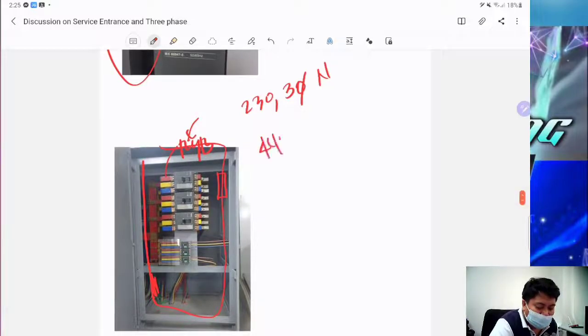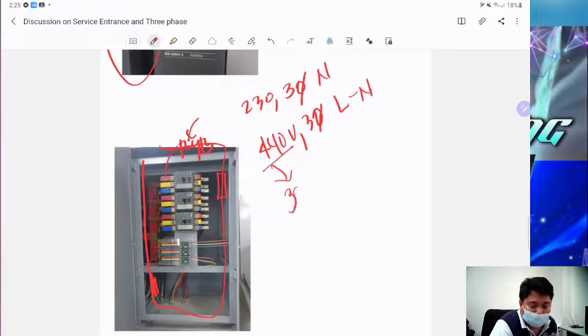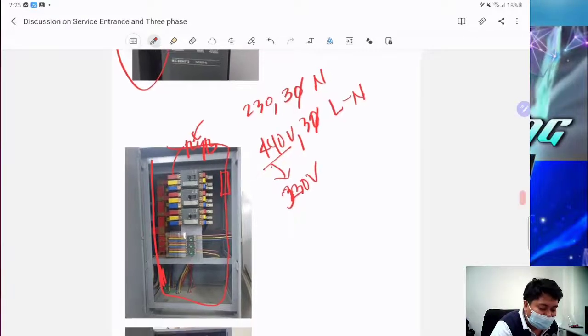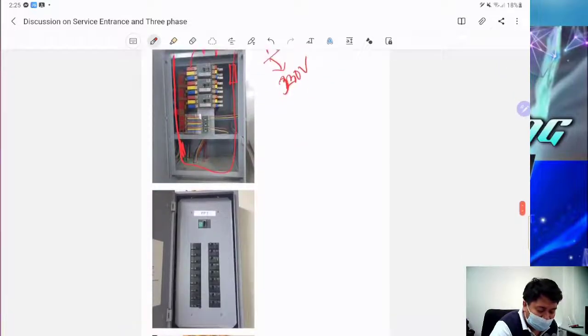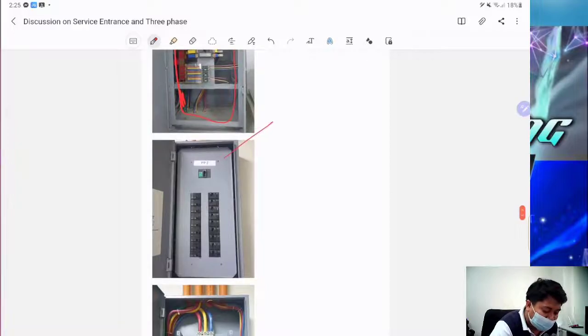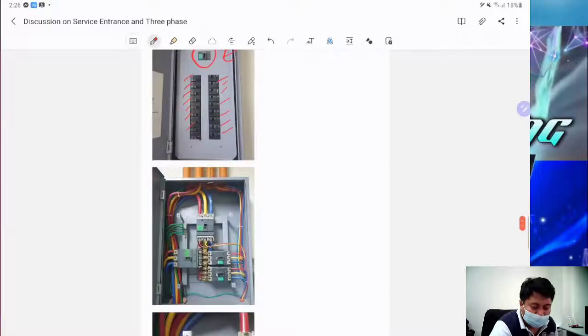But if we have a 440 volt 3-phase system, we can use a line to neutral configuration here, because once you have a line to neutral connection for 440 volts, we can obtain 230 volts. Okay? And then this is a sample of power panel 2, wherein we have the dead front cover, then the main, then these are the branch circuit breakers. And this one is also what we call a panel board. As you can see there, still following RYB. Then this is the molded case circuit breaker.